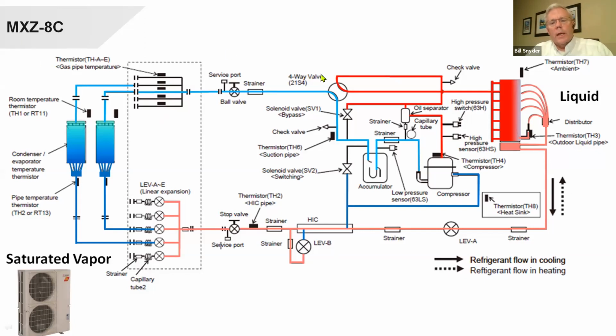But this particular one is the MXZ8C. This is the 4-ton unit with the branch box. This little dotted line here indicates the branch box. All this over here is inside. Everything from these service valves is outside. We have the compressor here. Like we talked about earlier, we've got a suction line, a discharge line, and this other line coming in, adding a little saturated vapor back into the compressor if needed.